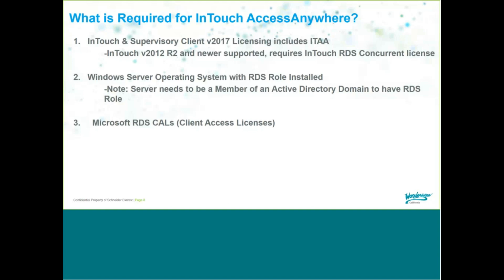Okay, and then the InTouch licensing is concurrent. So if you've got maybe a total of 10 people that may need to log in at any given time, but you only have maybe 5 people on the shift, then you would just need 5 licenses, and the 10 people would share those 5 licenses. So it's all concurrent based.